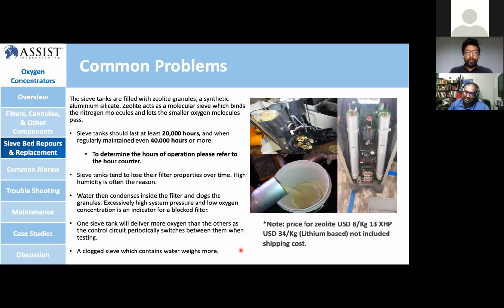So for the sieve tank, if the humidity is very high and it has been absorbed by water, the weight of the sieve tank changes as well. It ends up becoming very hard, and the pressure on the system will be higher. That's the reason that when you look at the high pressure section, your reading will be very high and you get a high pressure alarm, all because of this.